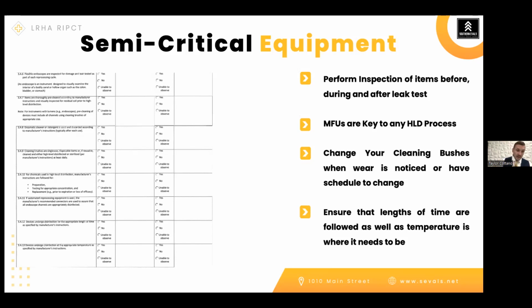You can see over here, it says to make sure that your brushes are changed appropriately. Many times we go in and the brushes look blown out, like we've been scrubbing floors or cleaning grout. If you notice that, have a process for the brushes that you use. Are they disposable? If they are, make sure you dispose of them between each use. If we are reusing those, make sure that at least they go through a disinfection process to make sure that they're cleaned.